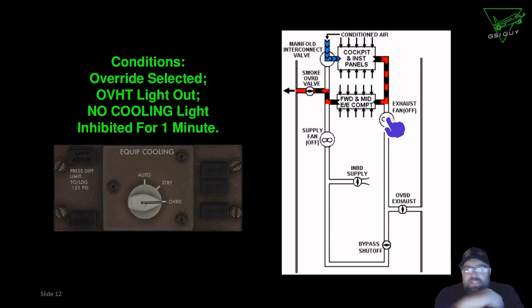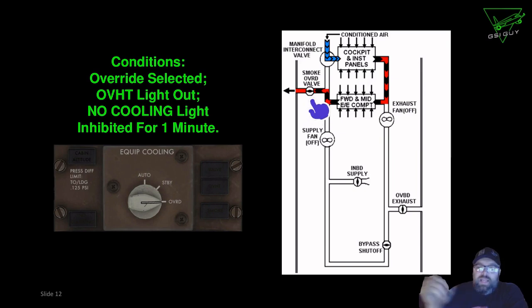Now, another thing that this schematic doesn't really have a good indication of is there's an airflow sensor in here. So there's an airflow sensor located like right here, right? And again, this is not to scale or anything. I'm just guessing where it would be in here, but it's got to be before the valve itself, because what happens is the valve opens, air gets pulled through, and then that airflow sensor is going to detect airflow coming through.